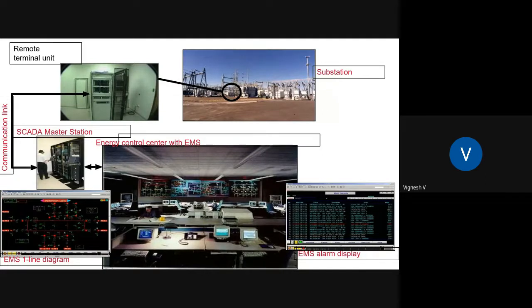We have the remote terminal units. You of course have the substation shown at the top, and then the remote terminal units, and then a master station connected with the communication link. The data is communicated to a control center which has the EMS running on it, so people can see what is happening on various transmission lines, what power flow is flowing on them, and what the generation is. Everything can be looked at on the screen at the control center. And if some control action needs to be done, the control center issues a control command back to the substation through the same communication link.